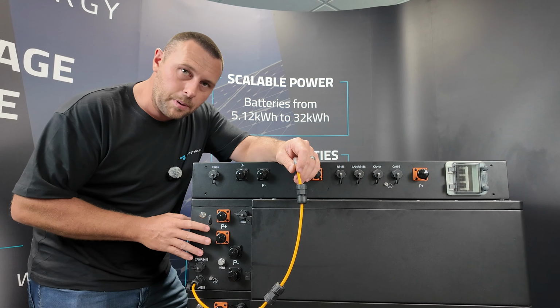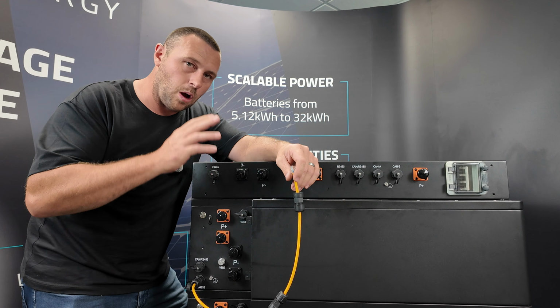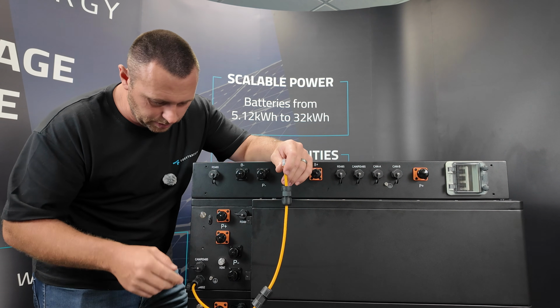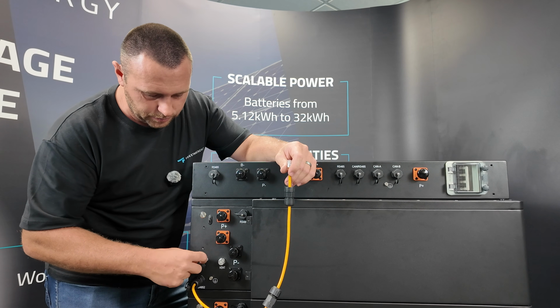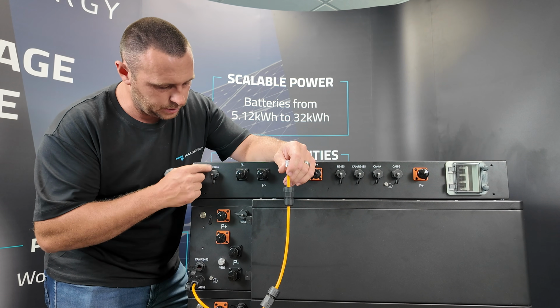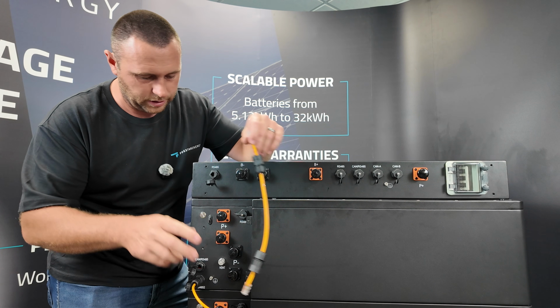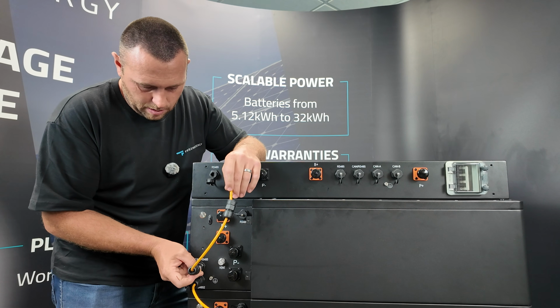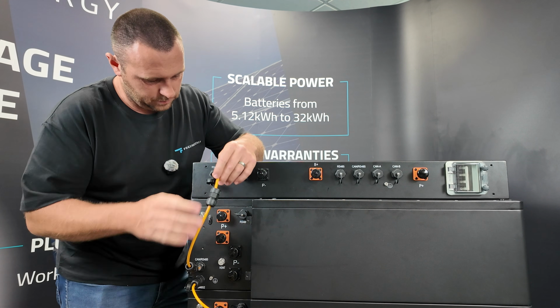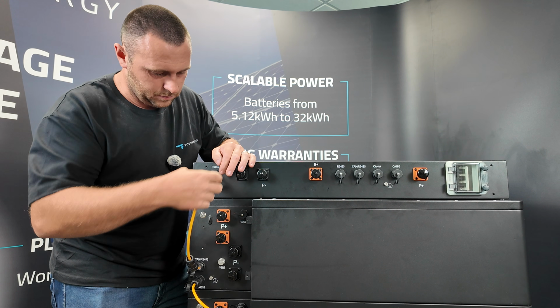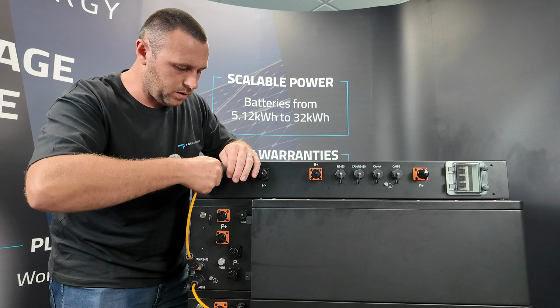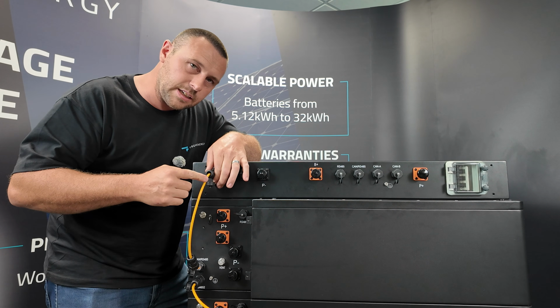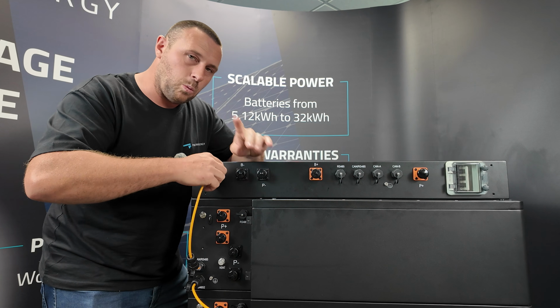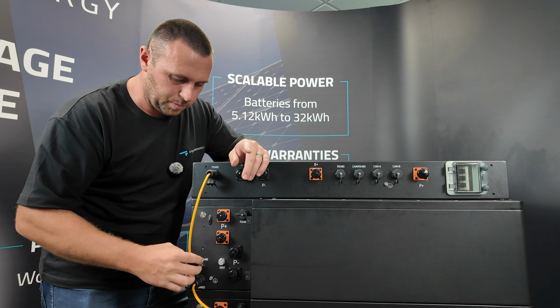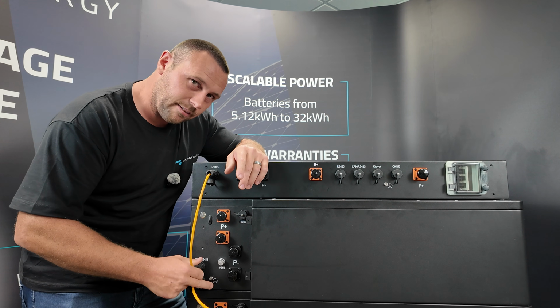For the top battery module to the control panel, wiring is slightly different. We're going to go from this CAN RS485 port up to this RS485 port on the top of the controller. Be aware that one of these communication leads, although they look exactly the same, one is very slightly longer for this purpose. Don't ask me how I found that out.